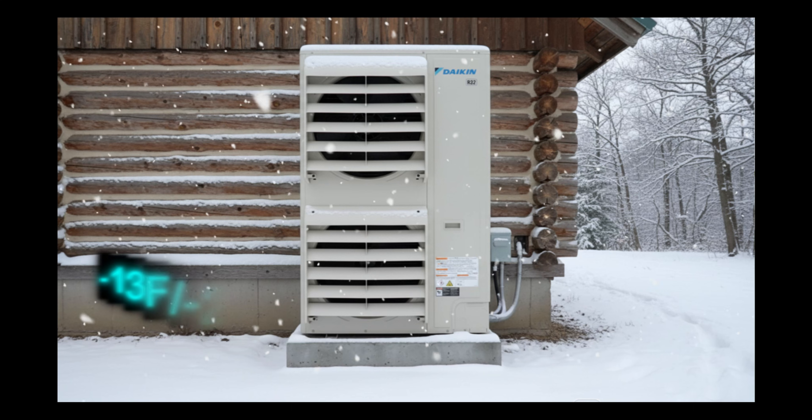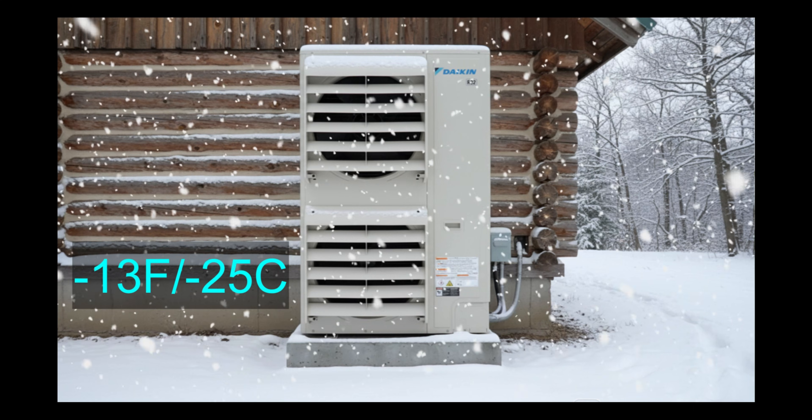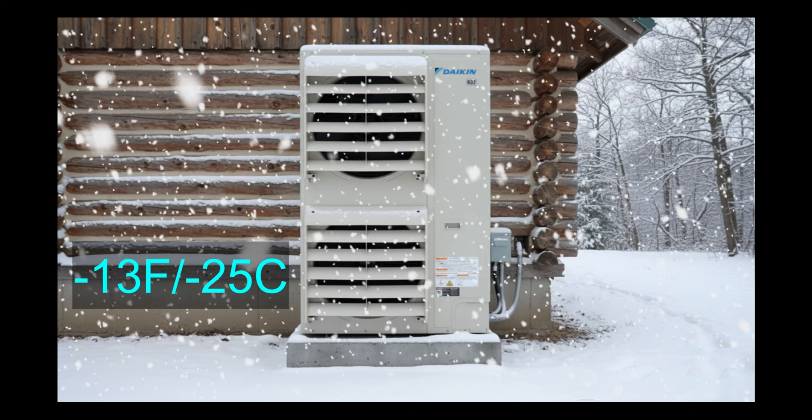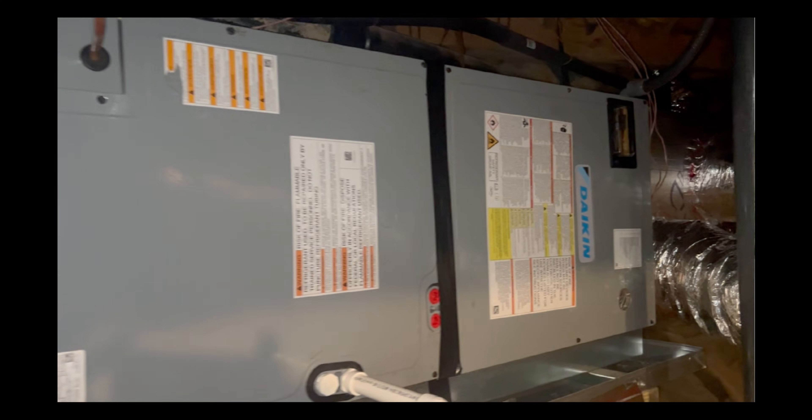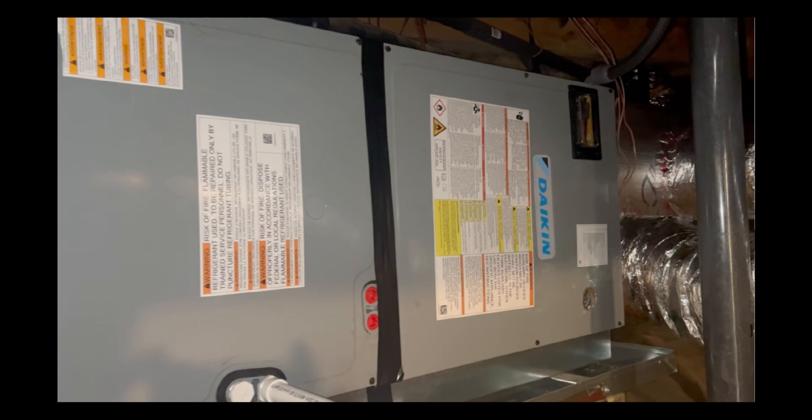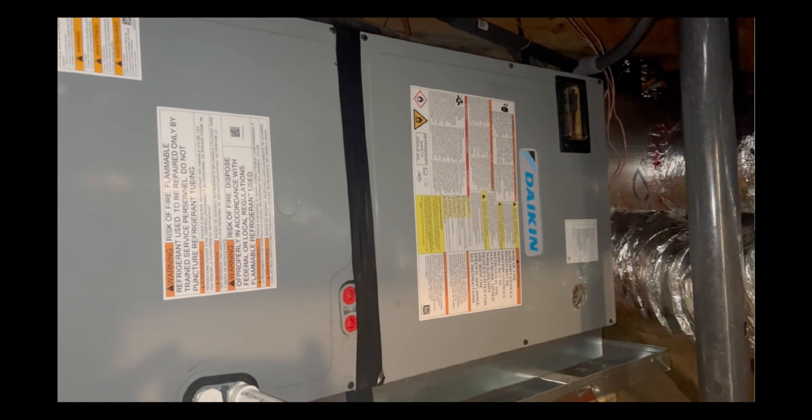Do you really need dual fuel? What does a typical heat pump do when the temperature drops so low that it can no longer generate heat? In the case of the Aurora, this threshold is minus 13 degrees. The answer is simple: it will switch to auxiliary heat. This particular system had a 10kW heater. On those very cold days it will rely on auxiliary heat. While the auxiliary heat is not very efficient, typical COP rating is one to one, it does the job, especially if the dealer properly sized the heater. And besides, you're not really limited to a 10kW heater; you can have a 15kW heater that provides even more heat.